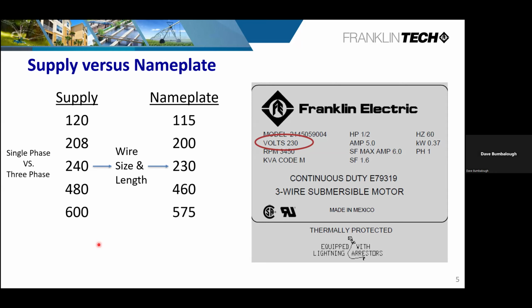And therefore you're buying more material. So that half horse that I'm showing you here in this little picture will now become basically a 3/4 horse motor that we're labeling a half horse, just to overcome this voltage issue here. But again, the Department of Energy, they are required to make sure that that voltage stays within plus or minus 5%. The Department of Energy has some rules and regulations on that, and if they ever get into that situation, I wouldn't hesitate to throw that up at them.